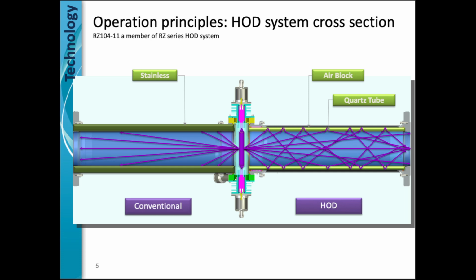With all its imperfections, the 100 millijoules was an average dose, meaning that half the time it worked and the other half it failed. It was elected to double up the size of the equipment and the lamps. At the much higher dose, the researchers achieved roughly 70% efficacy in the bio boxes. Next, the researchers set up the HOD UV at 100 millijoules per centimeter squared and achieved 100% settlement control.